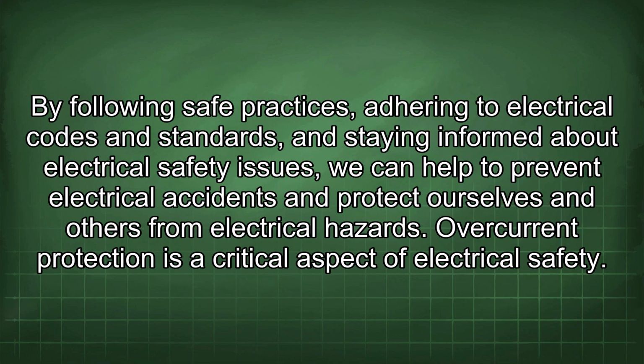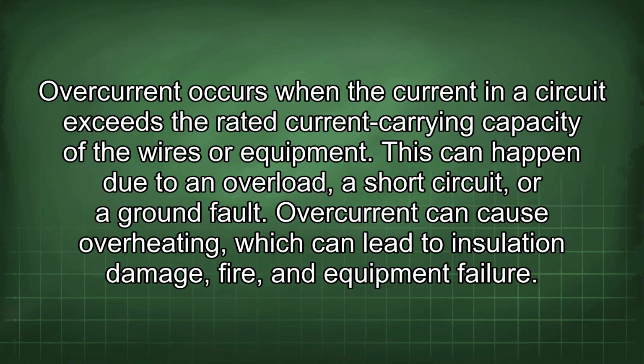By following safe practices, adhering to electrical codes and standards, and staying informed about electrical safety issues, we can help to prevent electrical accidents and protect ourselves and others from electrical hazards. Overcurrent protection is a critical aspect of electrical safety. Overcurrent occurs when the current in a circuit exceeds the rated current carrying capacity of the wires or equipment. This can happen due to an overload, a short circuit, or a ground fault. Overcurrent can cause overheating, which can lead to insulation damage, fire, and equipment failure.